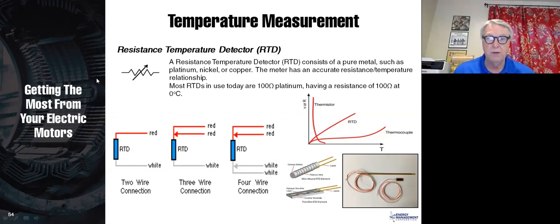Now, I want to mention that this is very important, how you hook the RTD up. If an RTD has two wires, and most of them don't, then you can simply measure the resistance, and that will tell you the temperature. The problem here, as you can see, is you're not just measuring the resistance of the RTD, you're also measuring the resistance of the wire between the input of the temperature detector and the RTD.